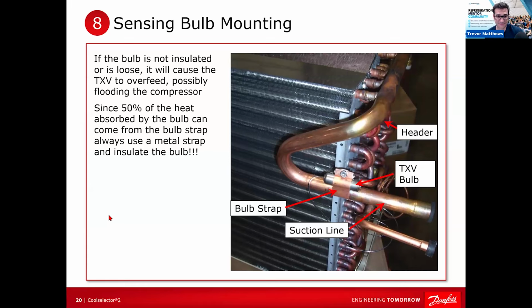Think about the sensing bulb. It's sitting on a pipe and there's only a little tiny bit of it touching that pipe. The rest of it is wide open to the air, right? And so that surrounding air, especially if it's moving, is going to have a large influence on it. So it doesn't take much of a temperature difference to cause that.